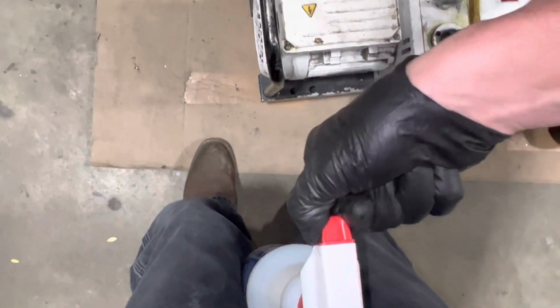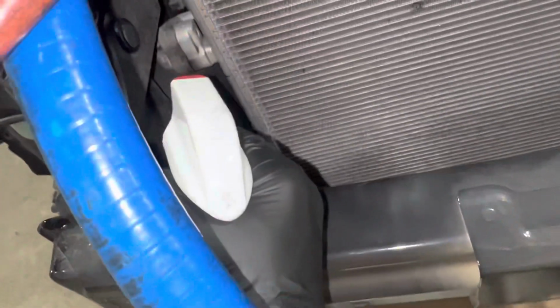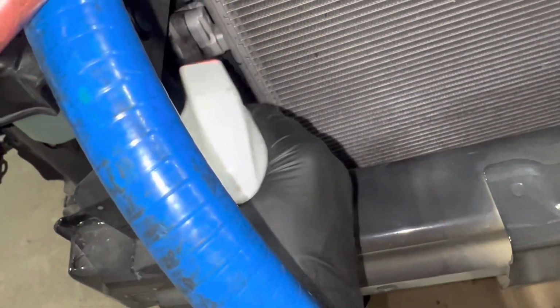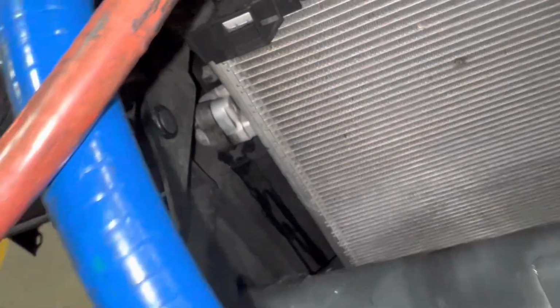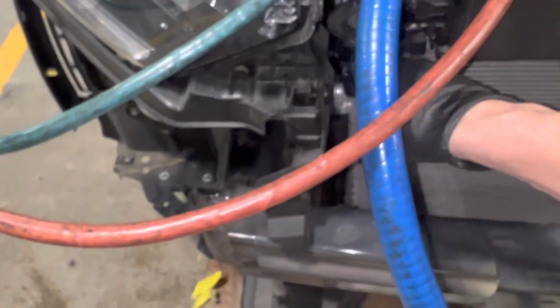I'm trying to get it set up right here. You just put that on there, and it stays wet for a very long time — that's the advantage of this leak detector solution. Then get your little mirror and put it on the back side if you can't see it with a flashlight, so you can see the back.